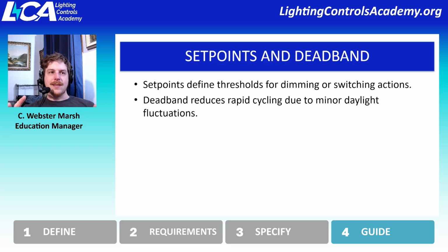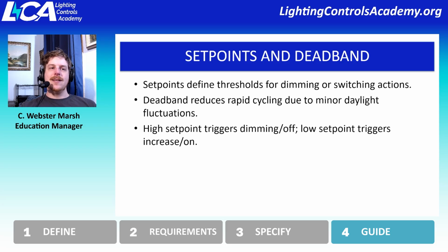that way the lighting is not just going to flicker on and off because of how variable that light quality is. So we might say between 3 and 7-foot candles instead of just right at 5-foot candles. And that's the deadband, 3 to 7-foot candles, which means that just don't react until it passes the deadband. So we might be targeting 5-foot candles as our set point, but really it's between 3 and 7-foot candles that you're going to not react, and then once you pass that threshold, you're going to react.